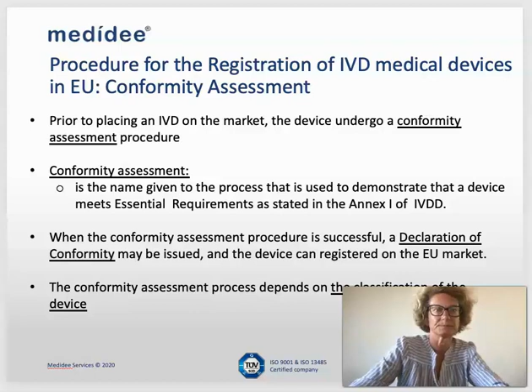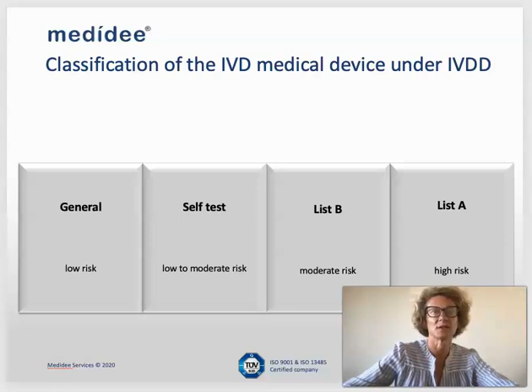The classification of in vitro diagnostic medical devices under the IVDD is specified in Annex 2 of the directive. First, we can see that the classification is based on risk. The highest risk are those devices which are found in list A. Then we have list B. We have the self-test devices, which are considered low to moderate risk. And then we have the general devices, which are devices of low risk. To give you an example of the tests found in each of those lists: in list A, we have tests which are considered high risk, such as the ones used for blood grouping under the ABO system, and also devices which detect HIV or hepatitis.